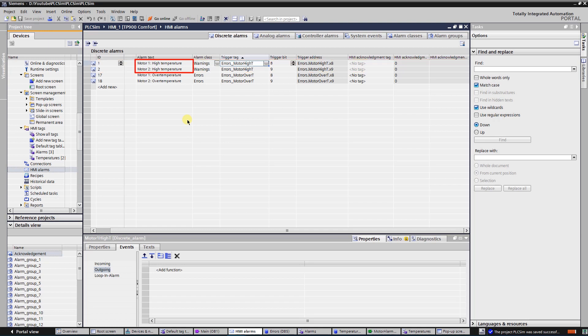Alarm text is the text that will be displayed for the operator. Alarm class is warning, which means the background of these two alarms will be yellow, and they do not need to be acknowledged or reset in the PLC.